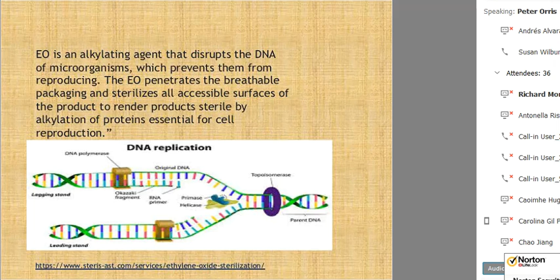As I indicated a moment ago, most of it is used in the creation of ethylene glycol on an industrial level. It is a direct alkylating agent that disrupts the DNA of microorganisms, and that's how it primarily has its sterilizing effect. Most of it was used in these rather small-sized ethylene oxide hospital sterilizers to sterilize packets for the emergency room, for the operating room, or any other materials that could not be put into an autoclave.